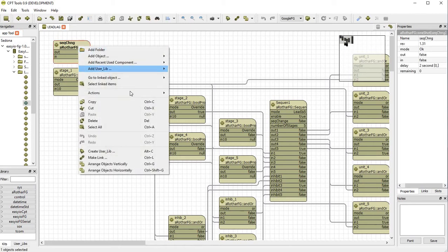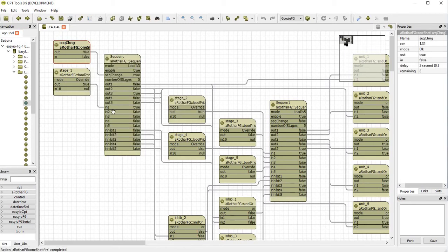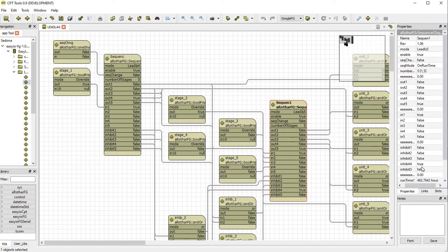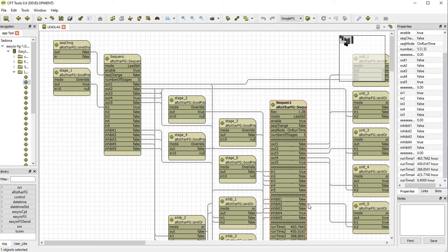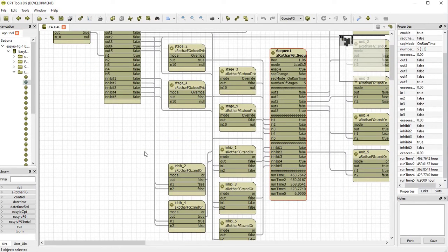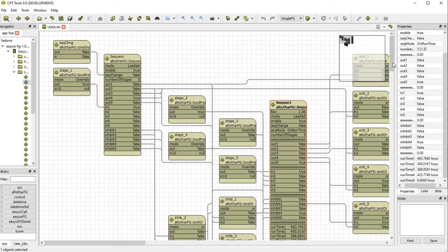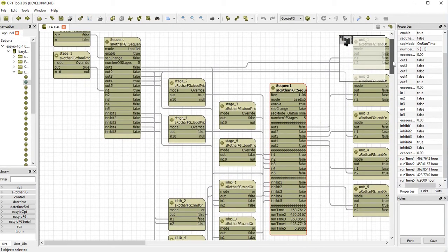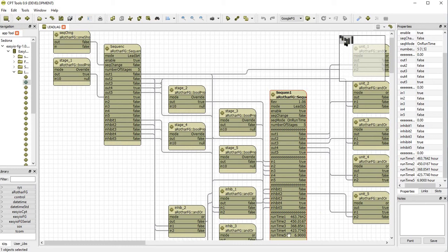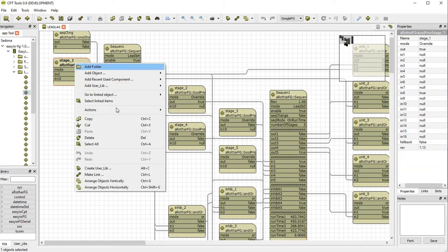If we run a sequence change to our lead chiller, 4 will now start up and 5 will remain on as it has the least amount of run hours. I'll expand this at 6. So if we ran another sequence change and the lead was 5, we would have a change where 5 continues to run as the lead, but 3 will start as the following chiller.